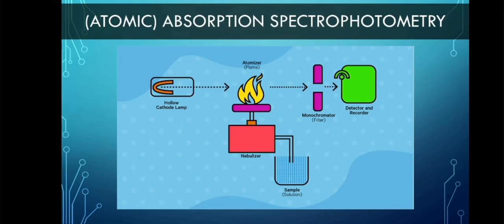Individual elements will absorb wavelengths differently and these absorbances are measured against standards. As we measure samples, we use standards to compare whether the machine is functional. When you run the standards through the machine and it gives you a value within the normal range or abnormal control, then you can still use the machine. It's like a detector whether your machine is still usable. Standards are usually given by the company of the reagents we use.